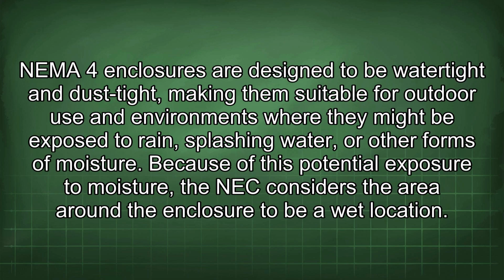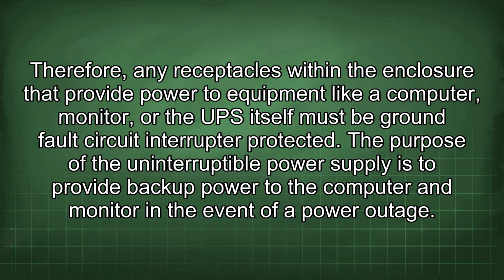NEMA 4 enclosures are designed to be watertight and dust-tight, making them suitable for outdoor use and environments where they might be exposed to rain, splashing water, or other forms of moisture. Because of this potential exposure to moisture, the NEC considers the area around the enclosure to be a wet location. Therefore, any receptacles within the enclosure that provide power to equipment like a computer, monitor, or the UPS itself must be ground fault circuit interrupter protected.